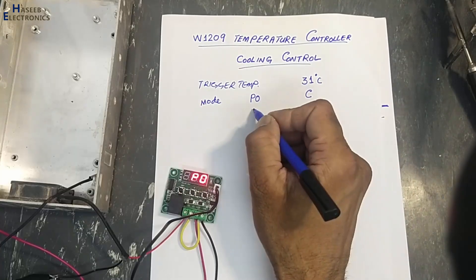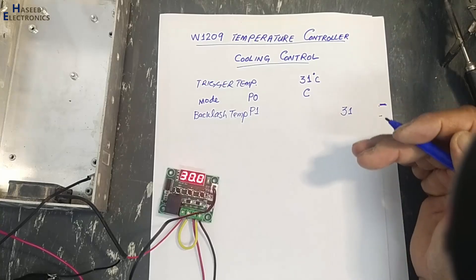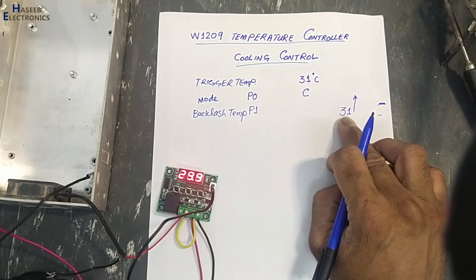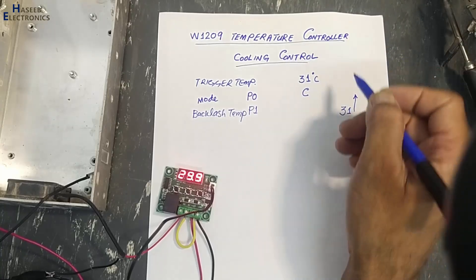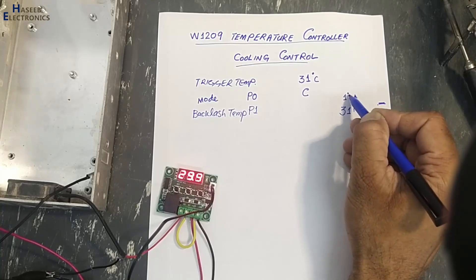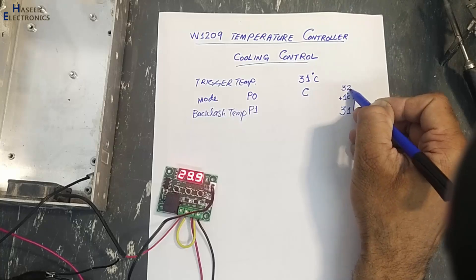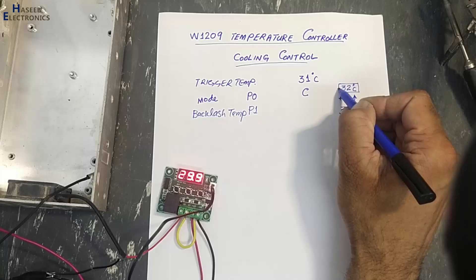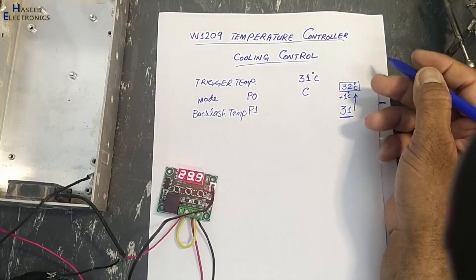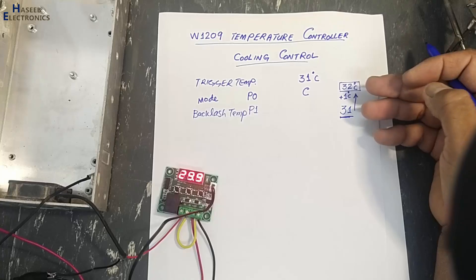Then P1 is the backlash temperature. 31°C is the lower limit — how much increase we will allow is the maximum cooling window. For example, I want to control 1°C, so plus 1. We can say 32°C is our higher level.